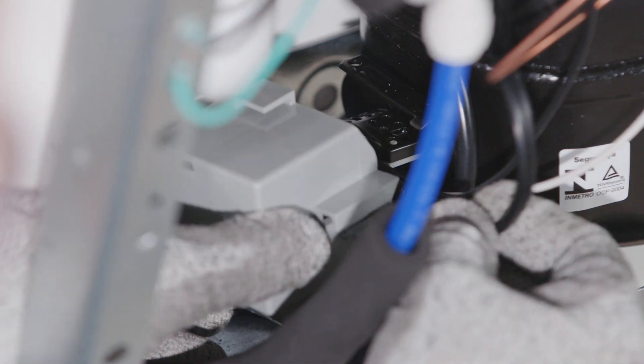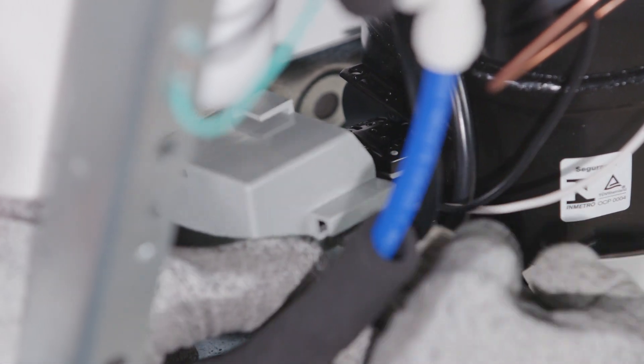If the readings are equal, place the overload onto the top coil post, then place the relay onto the bottom of the two coil posts. Snap the relay cap back onto the compressor. It should be secure after you hear two clicks.